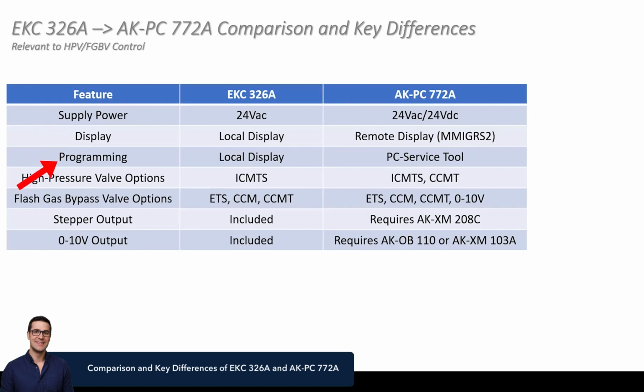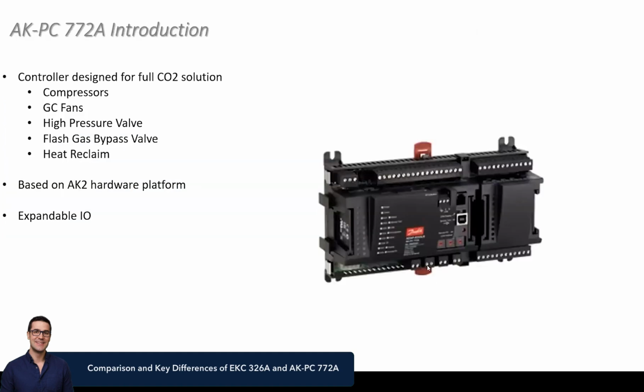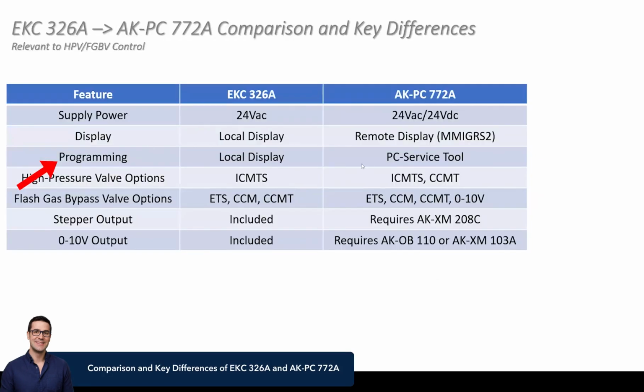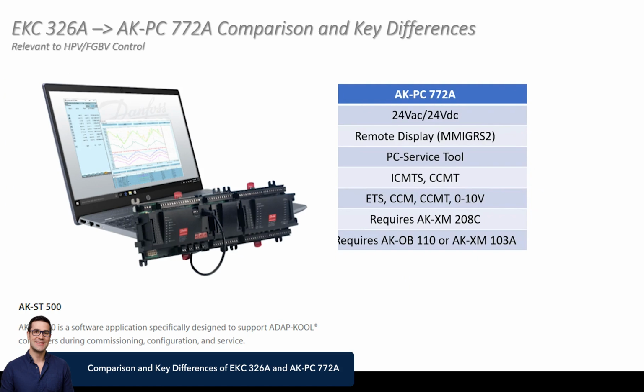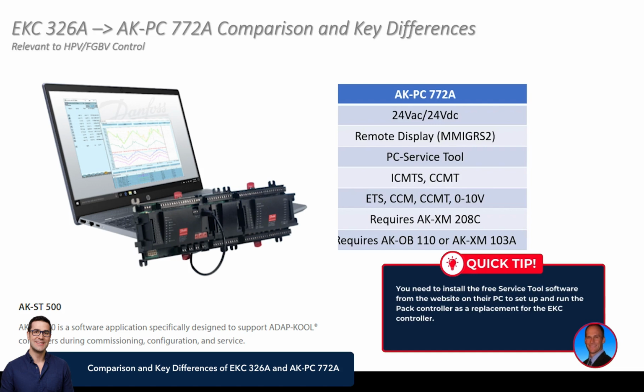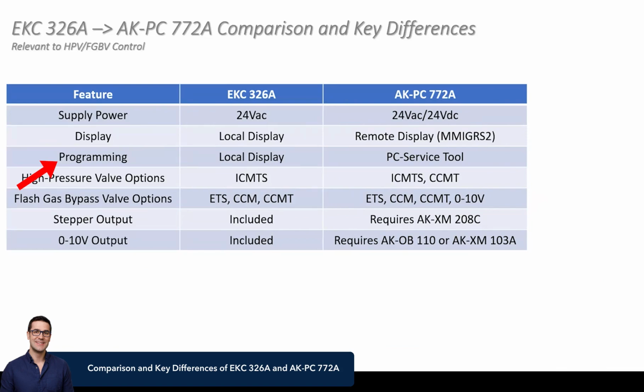The display and programming, so you guys can see here, there's no built-in display like we had on the 326, so it wouldn't be a matter of pressing buttons to set that up. We're now moving on to a pretty standard piece of equipment or program that we call service tool, that we use with any of our pack controllers. So that would be probably one of the biggest things that the guys would have to prepare for, the fact that they'd want to install this. It's a free download from our website, so it's not that it comes at a cost, but they would need to have this software installed on a PC so that they can set up and be prepared for running the pack controller in place of the EKC.